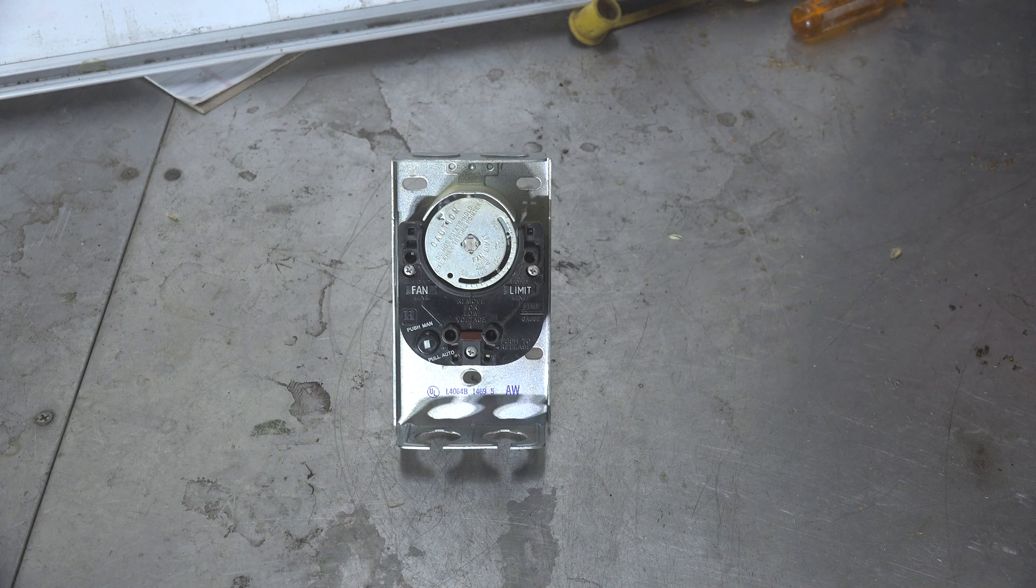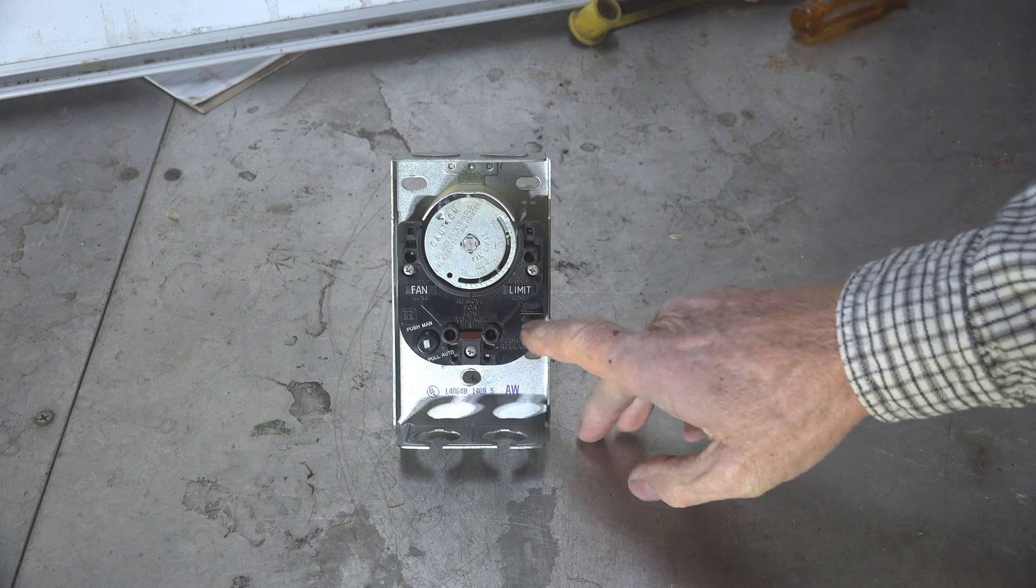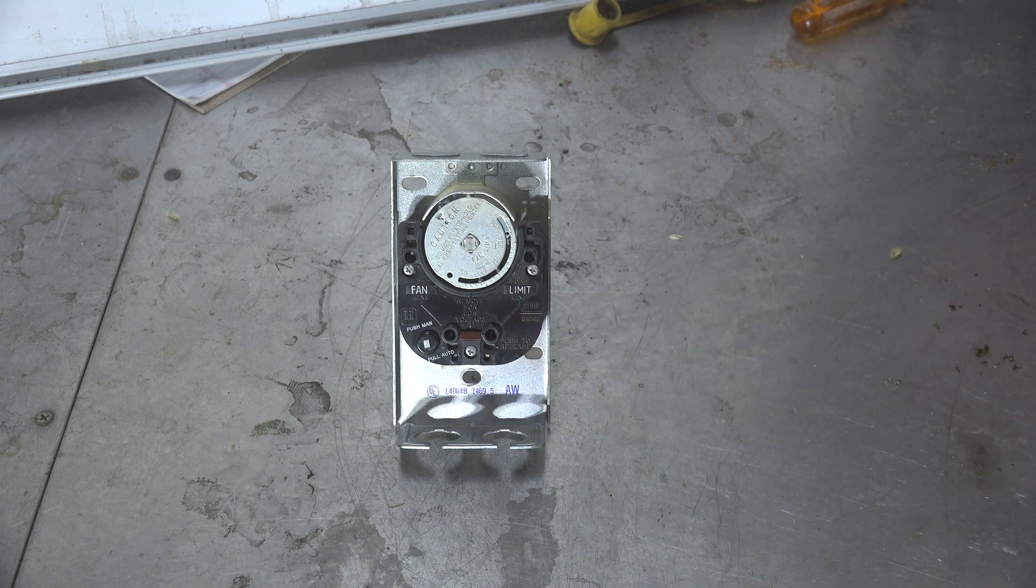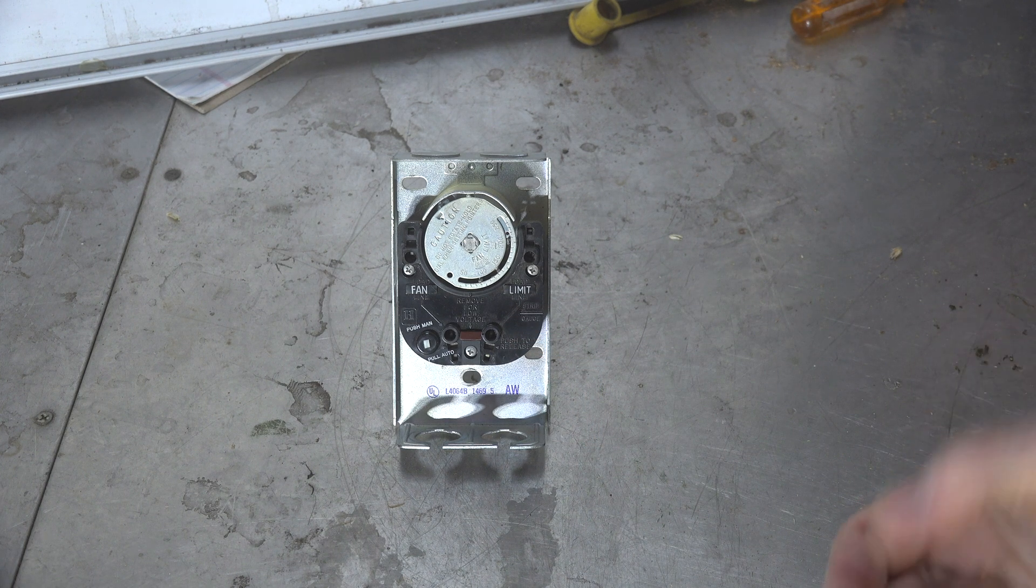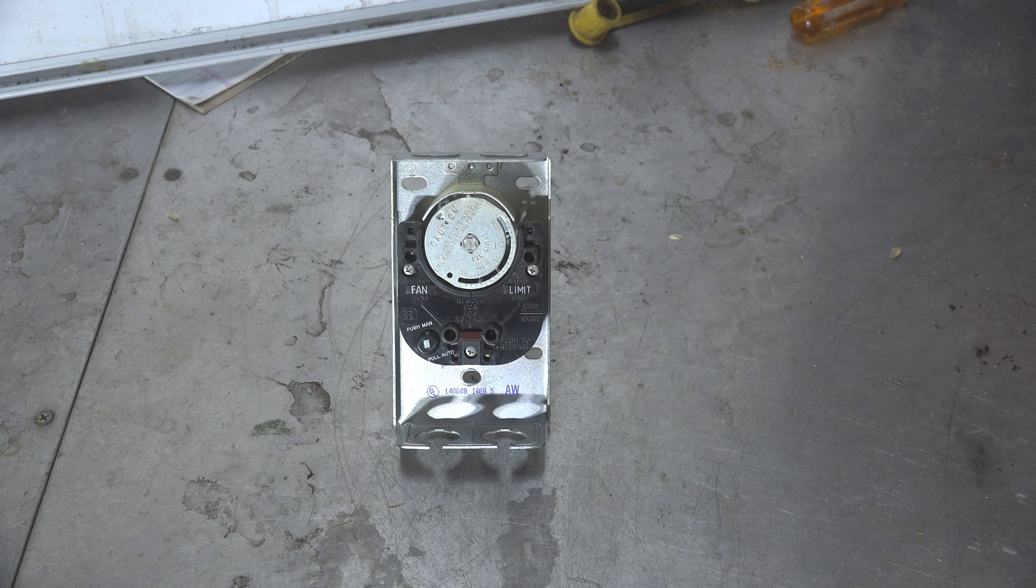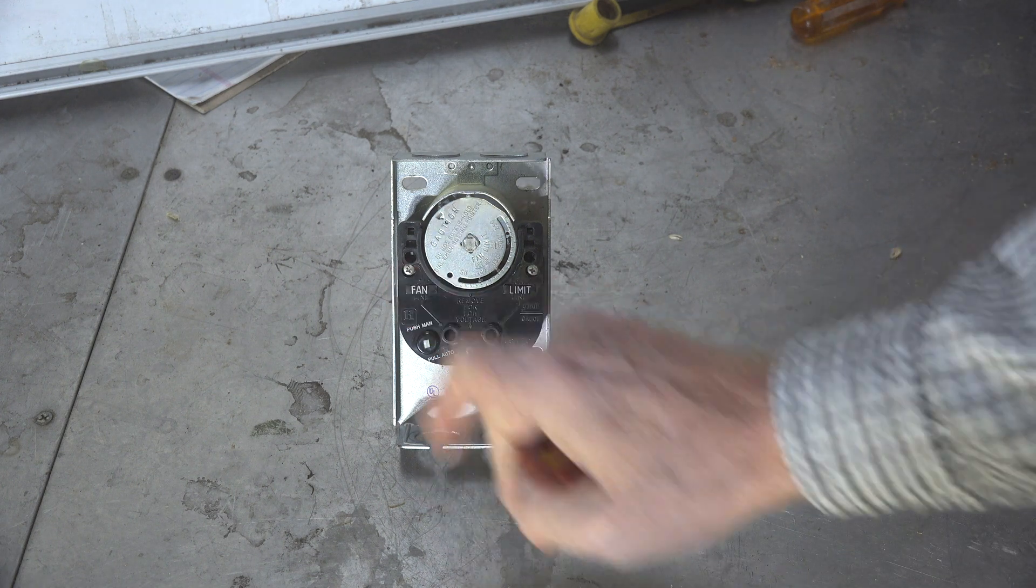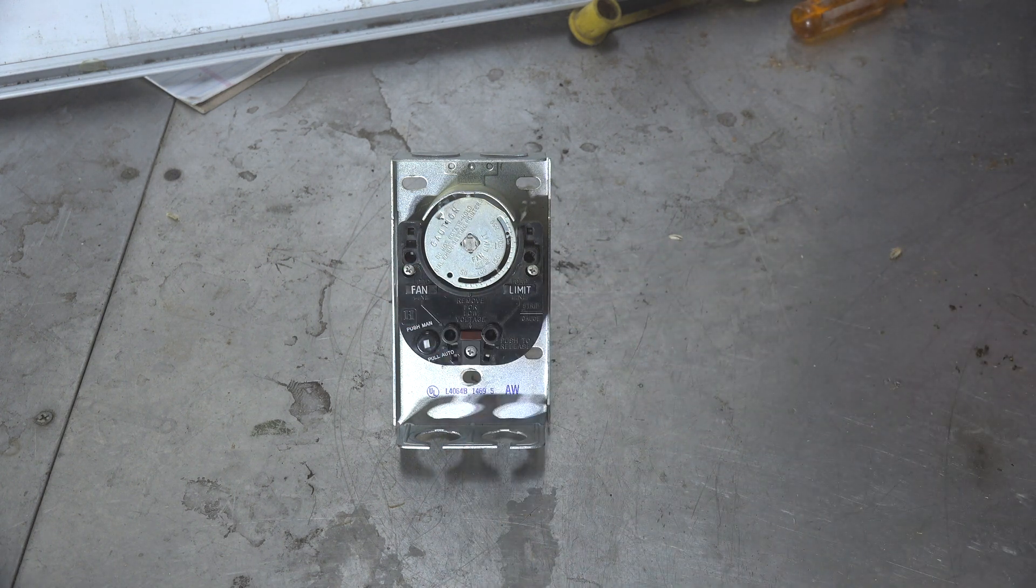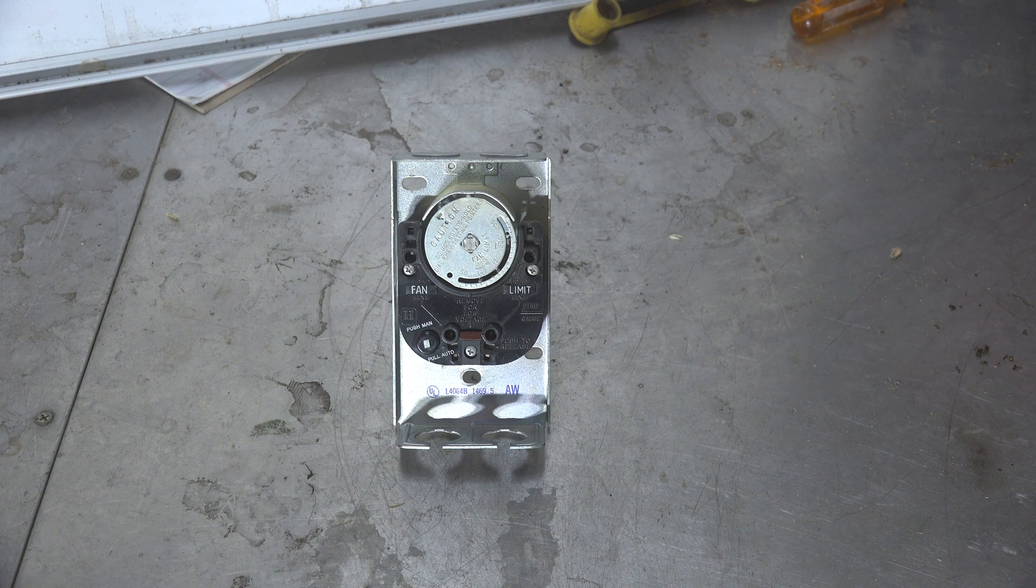On this side, if it gets too hot—like the fan doesn't work or the filters are plugged—then this limit is going to shut the burner off and leave the fan on, but the burner will shut off.